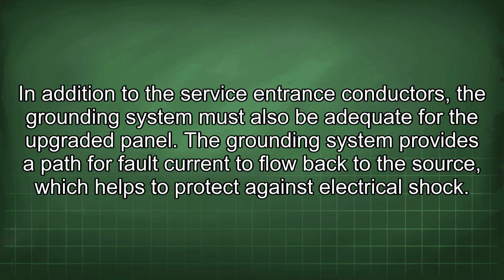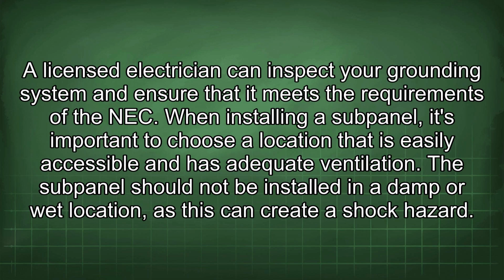In addition to the service entrance conductors, the grounding system must also be adequate for the upgraded panel. The grounding system provides a path for fault current to flow back to the source, which helps to protect against electrical shock. A licensed electrician can inspect your grounding system and ensure that it meets the requirements of the NEC.